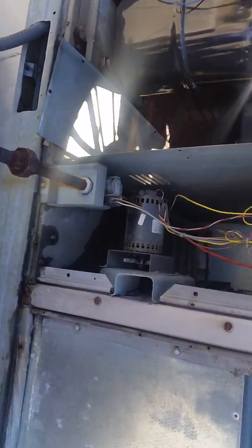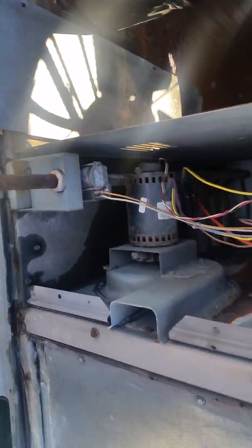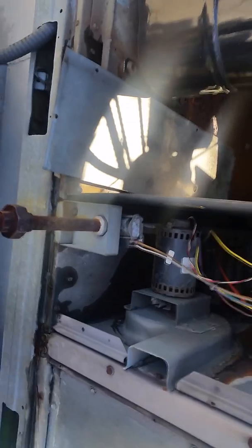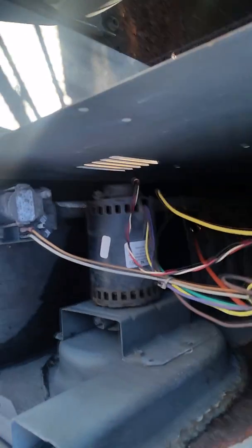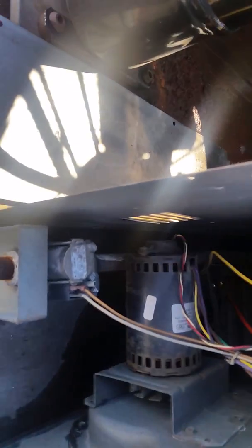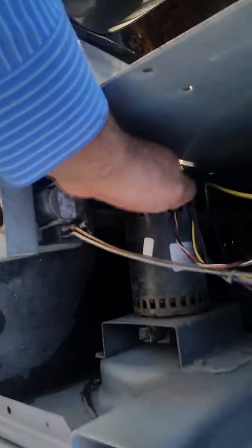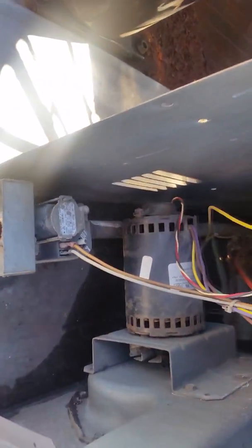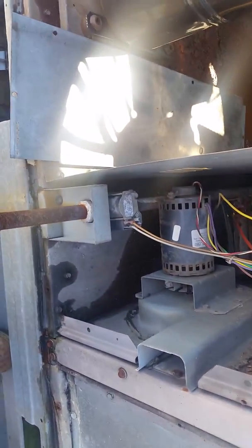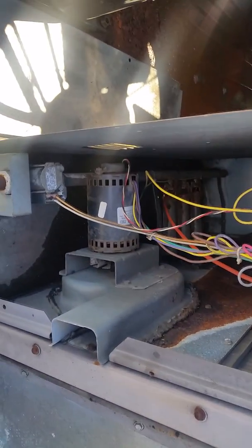The heater operation is not working. I turned on the gas. Somebody had the gas turned off, so for checking it out purposes, I turned it back on. I checked everything. It looks like we probably have a problem with this inducer motor, the combustion motor. Some heavy rust there, and possibly on the heat exchanger. That rust, I don't like the way that looks.